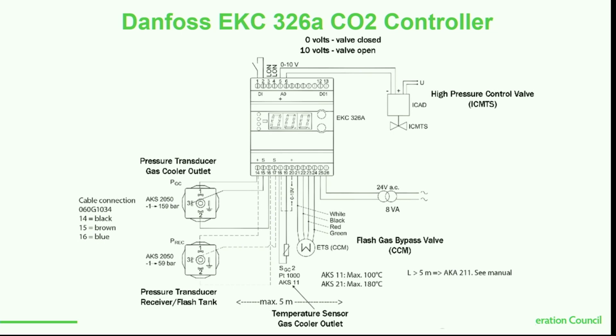We talked about every one of them, yes? Dude, start simple. If I walk up to a rack, you got a ton of these in LA, in Southern California. To me, LA is everything like south of Magic Mountain, right? But if I walk in, I have a Danfoss 326A and it says off, I'm in phase loss, because that's what it'll show me. All right, so make sure you're checking that. Again, it can be a simple ice cube relay, not really in phase loss. Compressor seems to be trying to work. Everything's shut down. I could simply have lost an ice cube relay. Start simple. The things that are most likely going to break. All right?